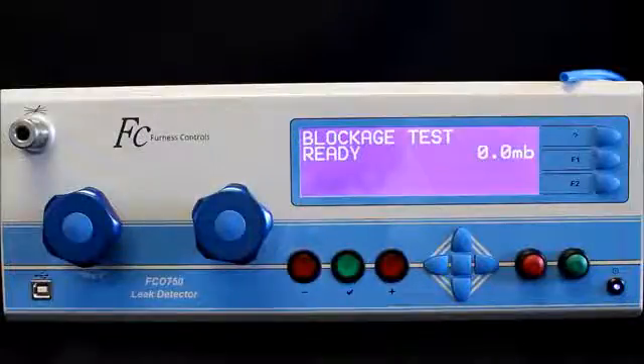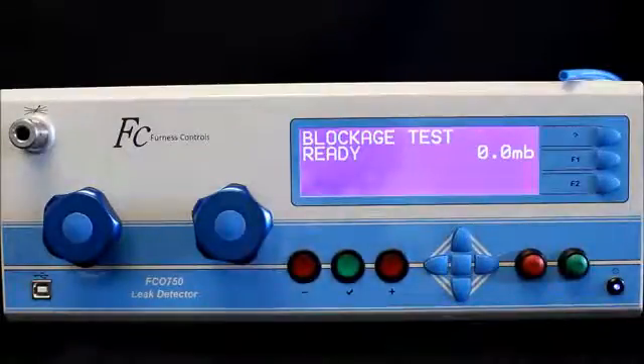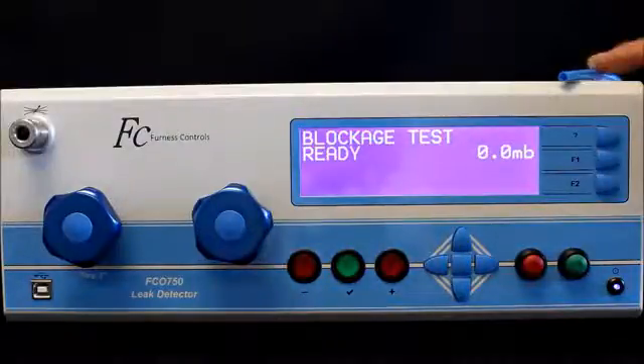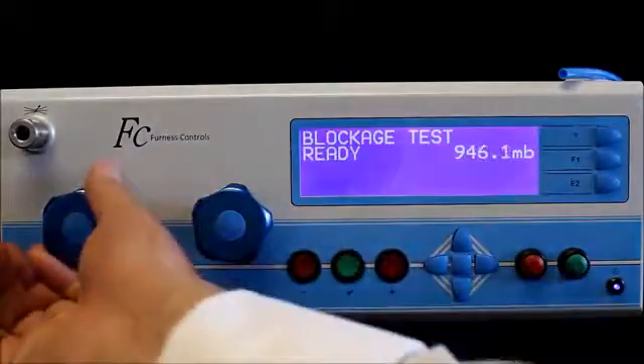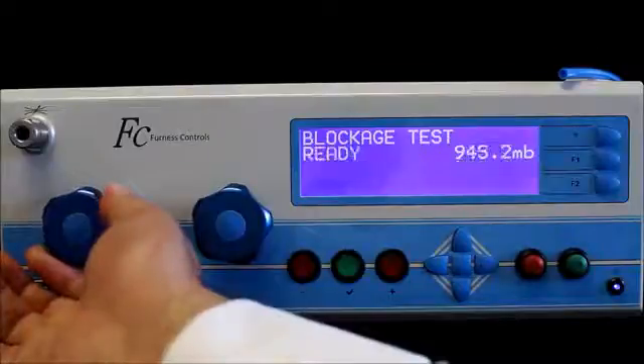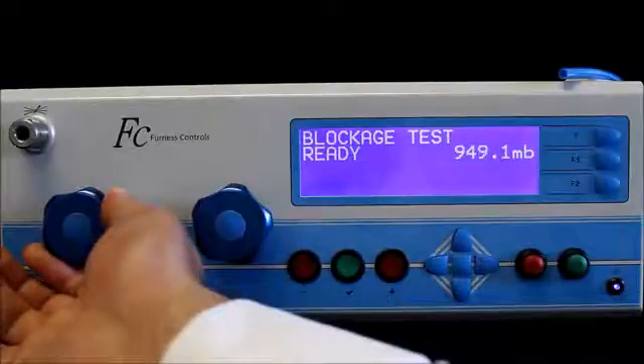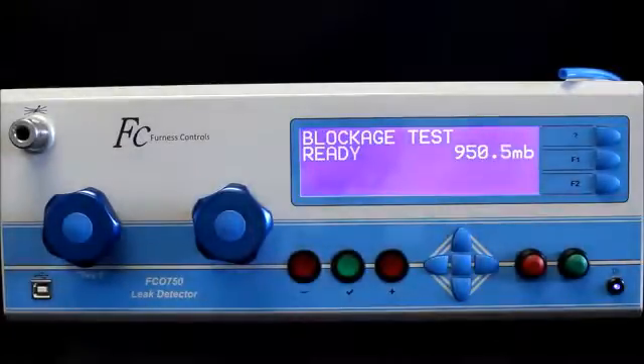I've set up the Furness Controls FCO 750 leak detector to do a blockage test. Here we have a piece of tube which is 6 by 4, so 4mm internal diameter, and we just need to practically set up a test to check whether this tube is blocked or not. I need to make sure that my regulator is set correctly — if it isn't, it lets me know. I'll bring that up to around the 950 millibar mark.